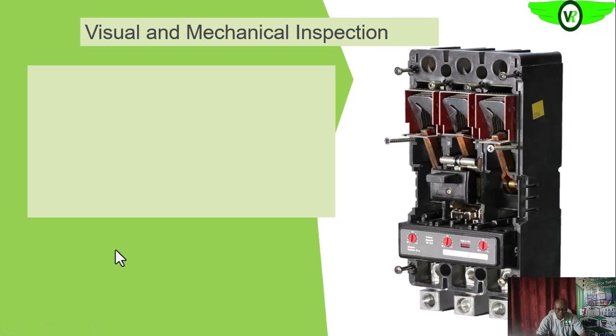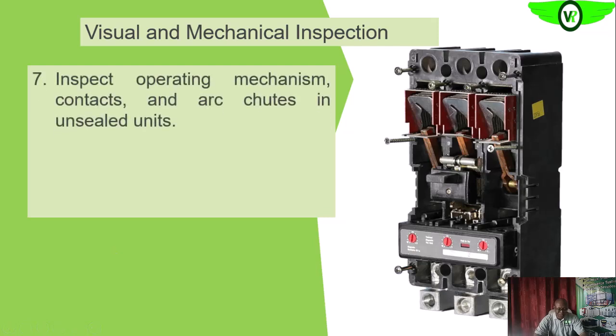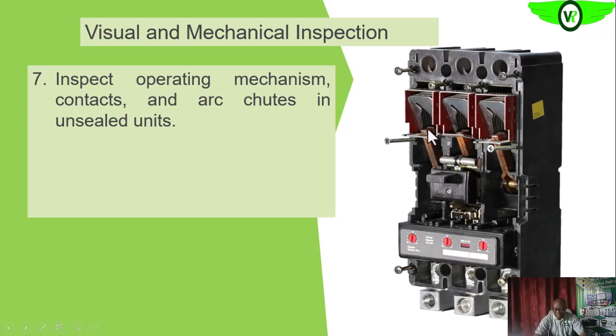Okay, so still on the visual and mechanical inspection, if it is possible to open the breaker, you can open it as you can see. Then you inspect the operating mechanism to see that it is functioning properly. Then the contacts, you need to look at them to see that they are free from debris and other metal oxides that will be deposited on the contact. If there are, we clean them. Then the arc chute is also free from contamination. This is the arc chute, okay, that they are free from contamination.